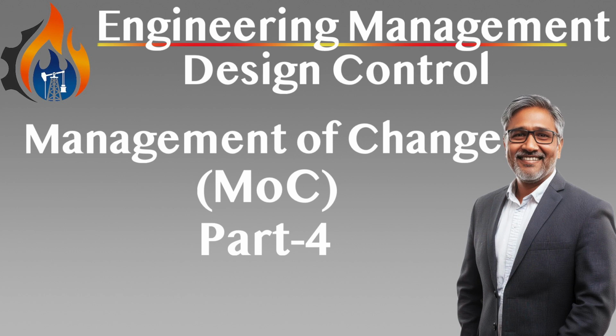Despite their often invisible nature, configuration changes can carry significant operational and safety implications. This procedure ensures they are managed with the same rigor and traceability as physical changes, protecting the integrity of critical systems such as emergency shutdown, ESD, fire and gas, process control, and safety instrumented systems.